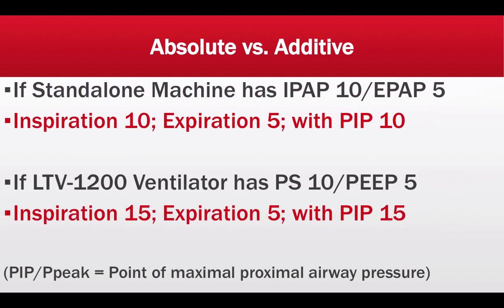So how does that translate into real-world application? If you have a standalone machine such as the BiPAP Vision by Respironics set to IPAP 10 and EPAP of 5, when the patient initiates inspiration, the machine will deliver 10 centimeters of water. When the patient exhales, the machine will deliver 5 centimeters of water pressure. Peak inspiratory pressures during inspiration would be 10 centimeters of water.